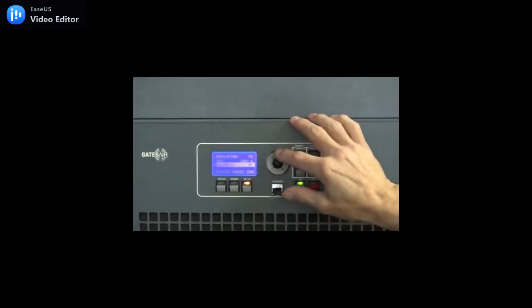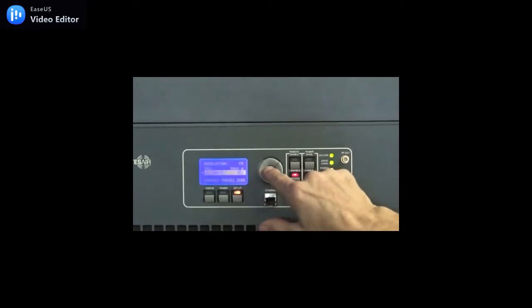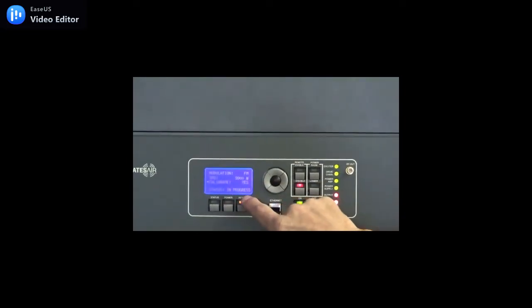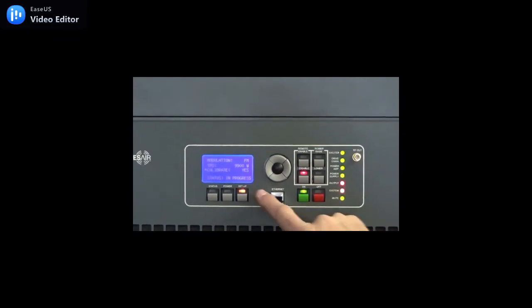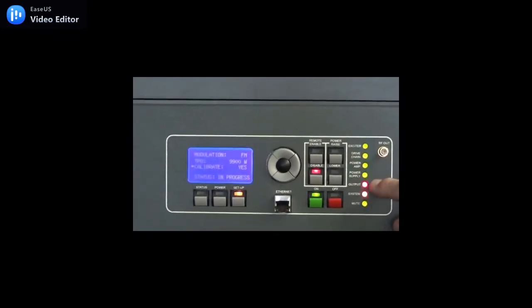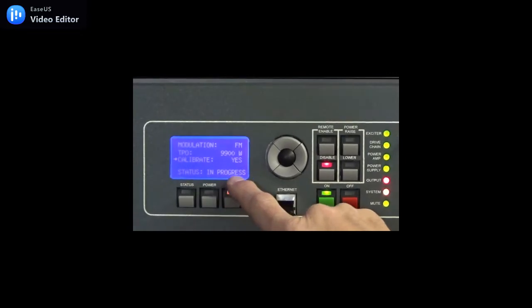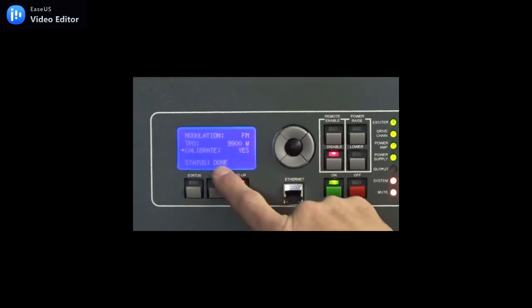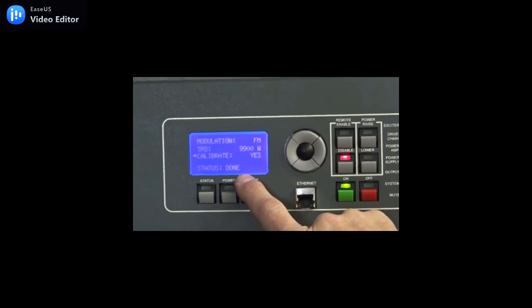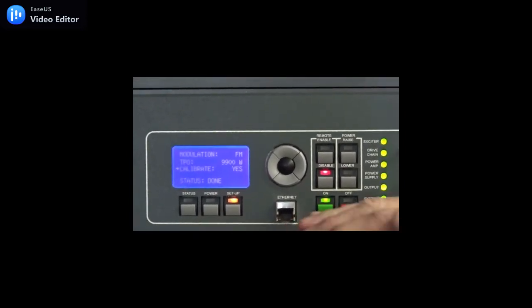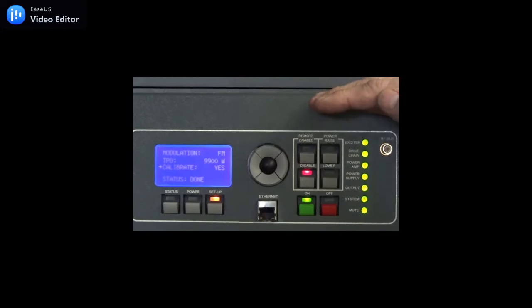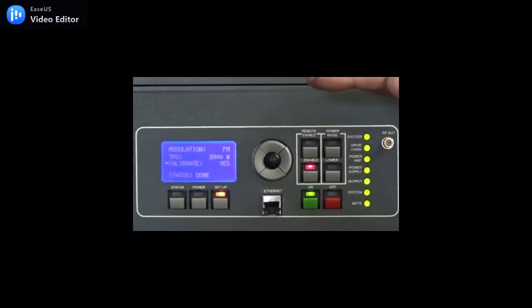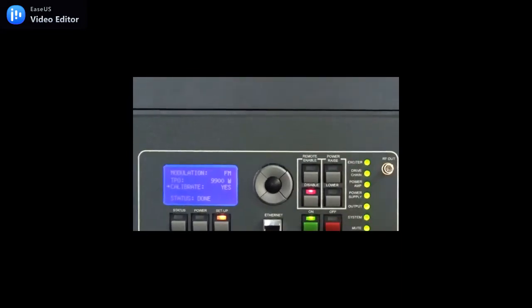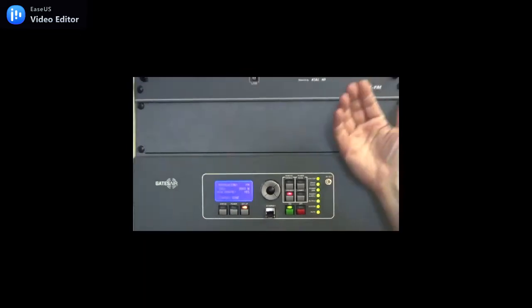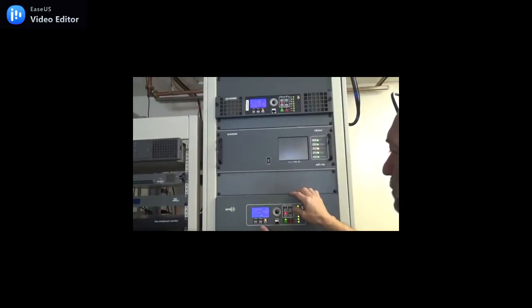So what it's going to do now is, I'm going to highlight this, I'm going to say yes. I'm going to press the button, and you'll see it says in progress. You might see the raise lower buttons light a little bit. It'll go through its procedure, and now it says done. So that has completed the power calibration for the forward and the reflected power calibration. It's done.